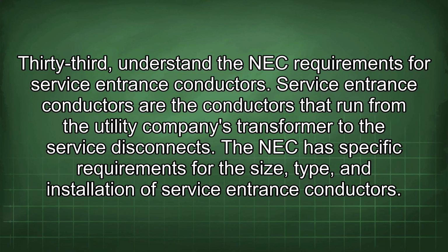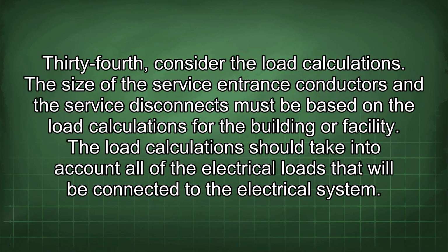33rd, understand the NEC requirements for service entrance conductors. Service entrance conductors are the conductors that run from the utility company's transformer to the service disconnects. The NEC has specific requirements for the size, type, and installation of service entrance conductors. 34th, consider the load calculations.